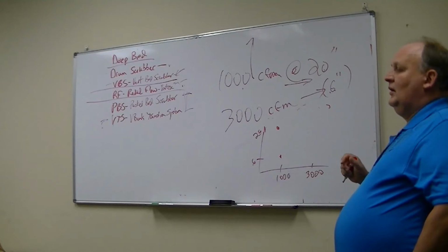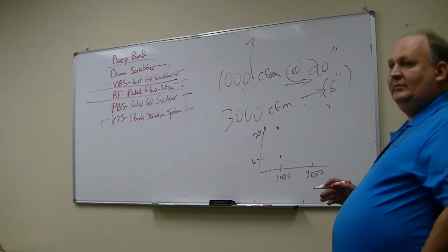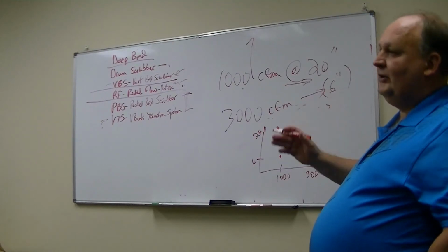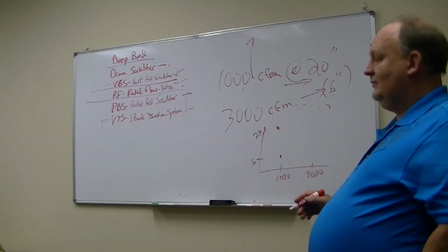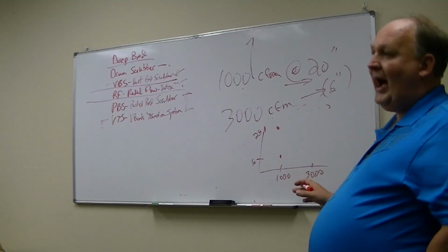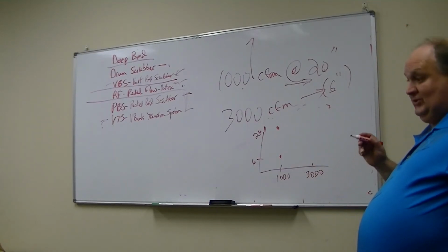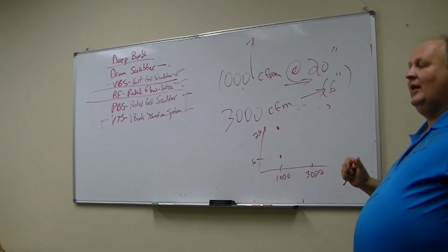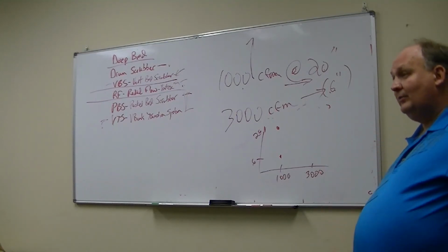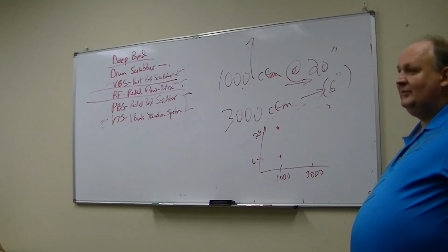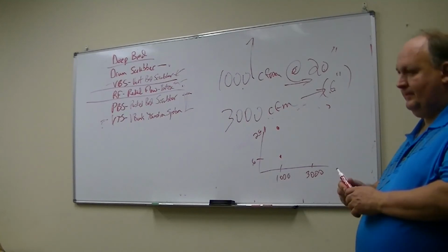Okay, we had a case up in North Carolina where the engineer literally wanted, I think it was 20 inches of water column. We repeatedly told him, no, you don't need this. We gave him exactly what he wanted. The airflow was super high, and it was super noisy as well, because this thing was taking off like a jet. And, you know, we documented, listen, we told you this was gonna be a problem. It's also extremely energy inefficient.